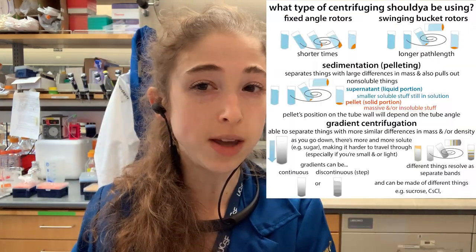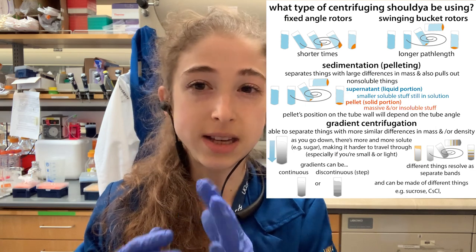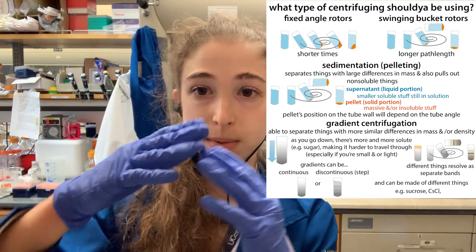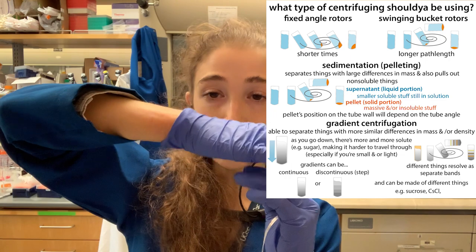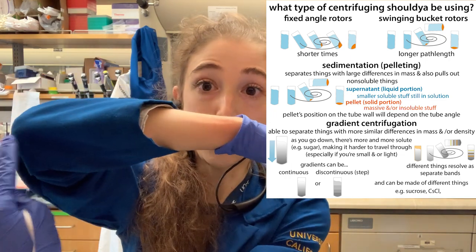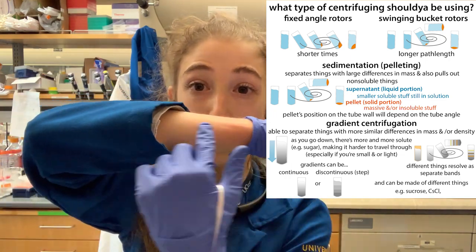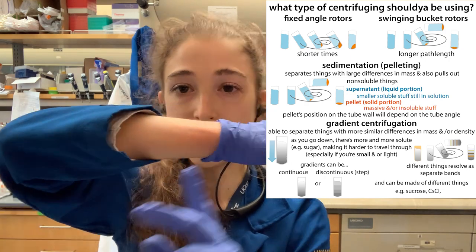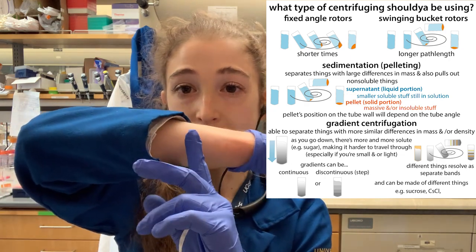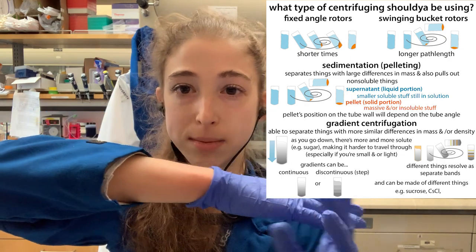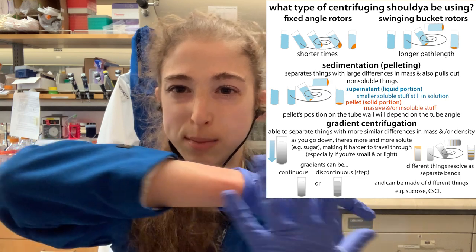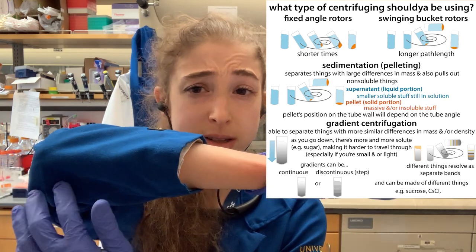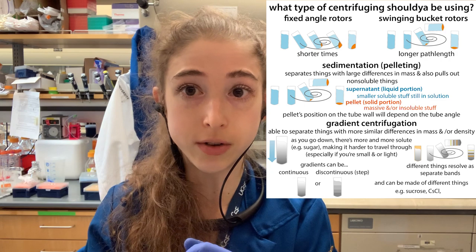When it comes to swinging bucket rotors, you'll often see the maximum force listed. That's because your tube is horizontal, and you're going to have a different force felt throughout the tube — the maximum force is at the bottom, the minimum near the top, and the average is somewhere between the two. Typically it's given in terms of the max when doing conversions.